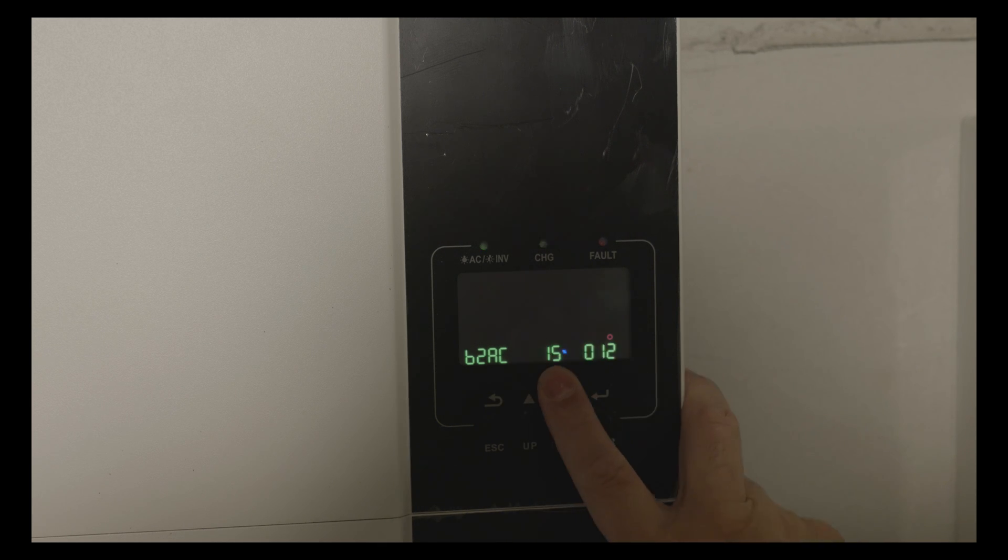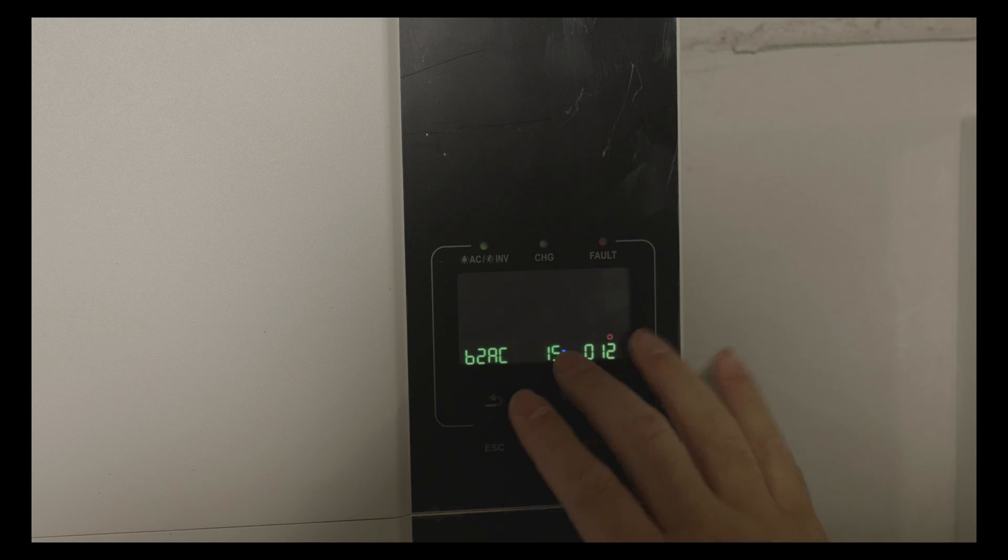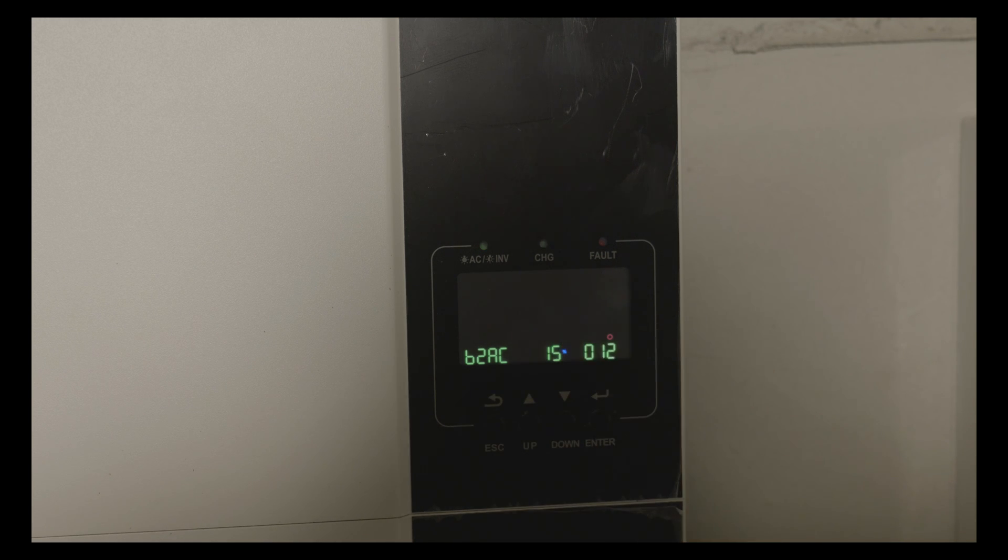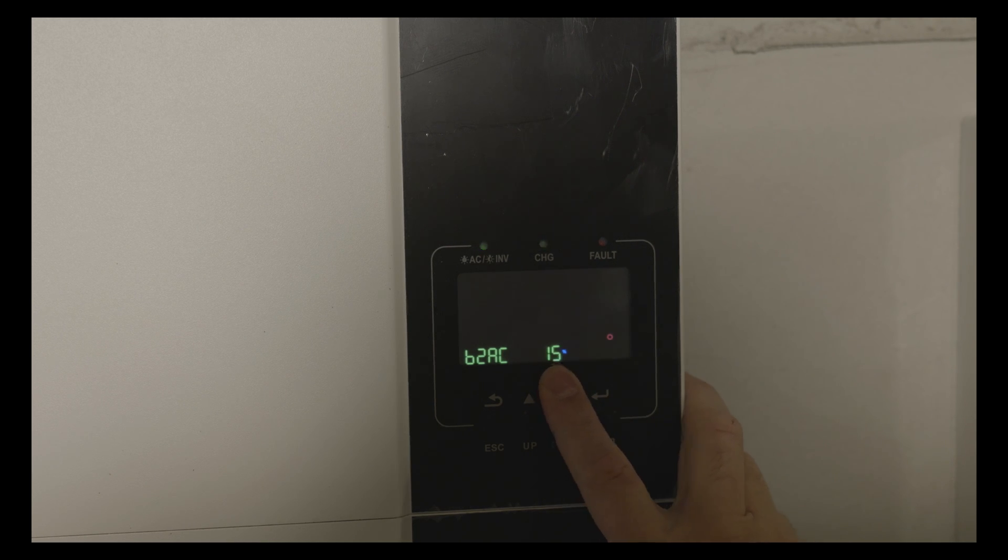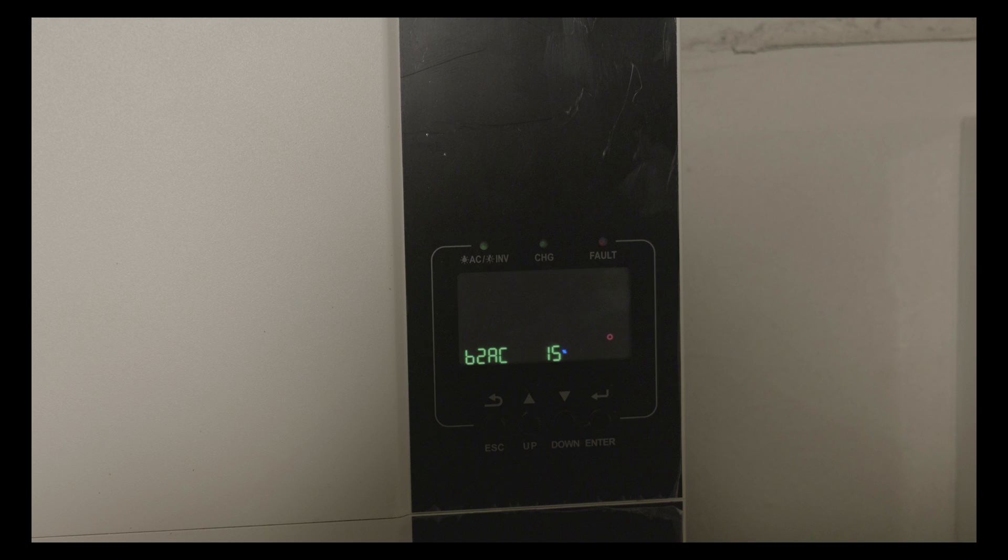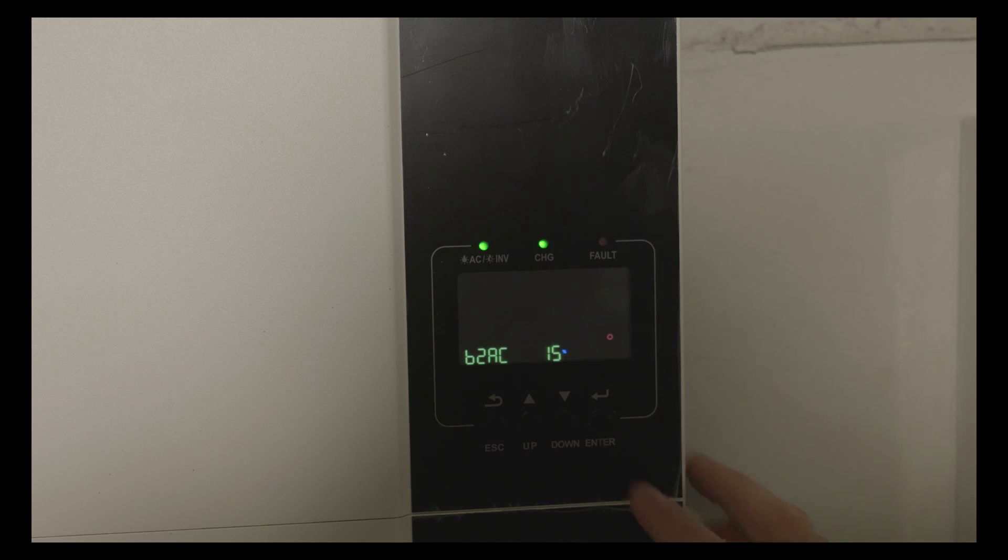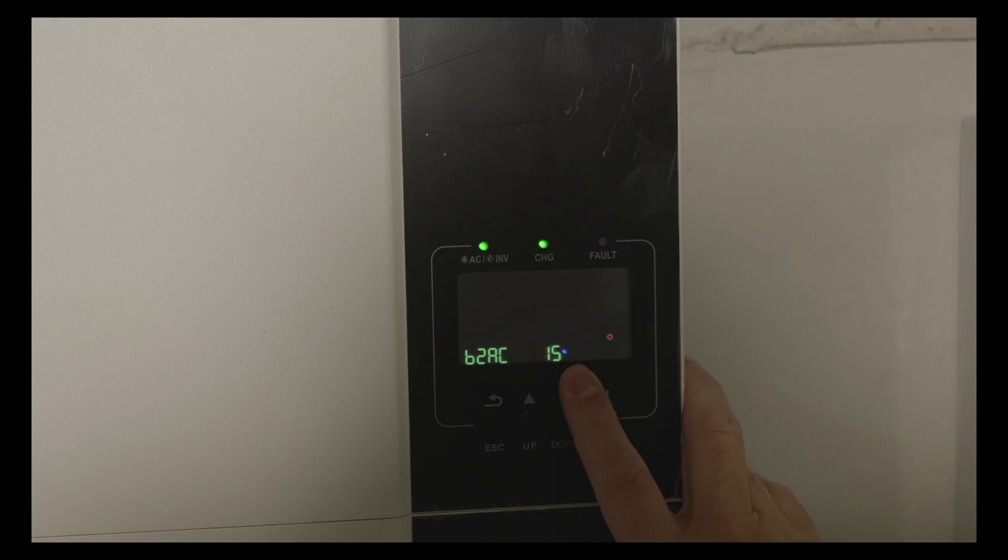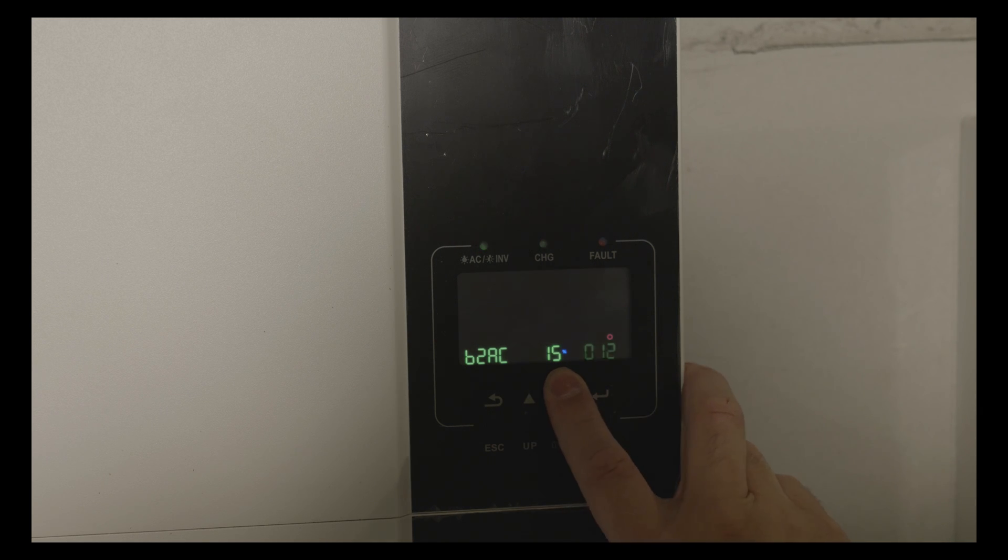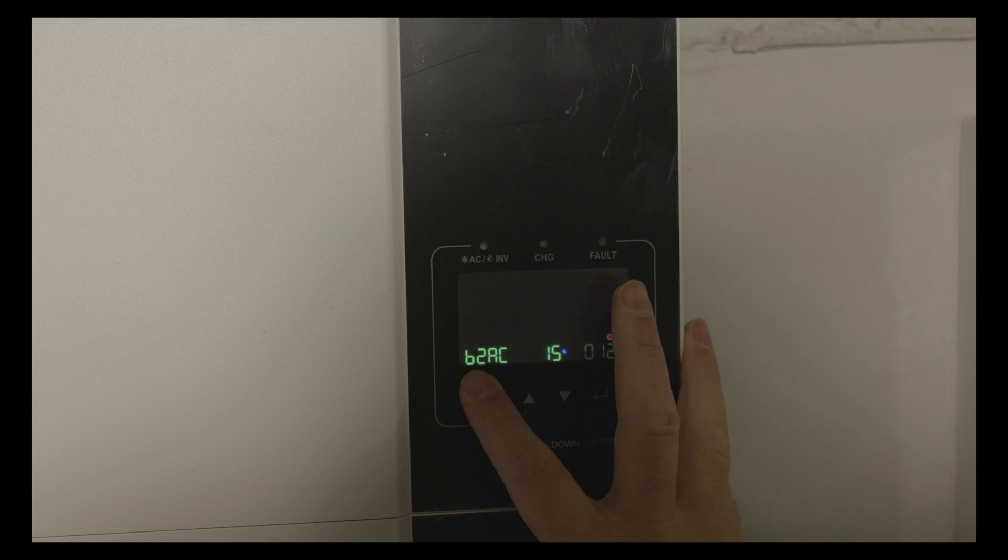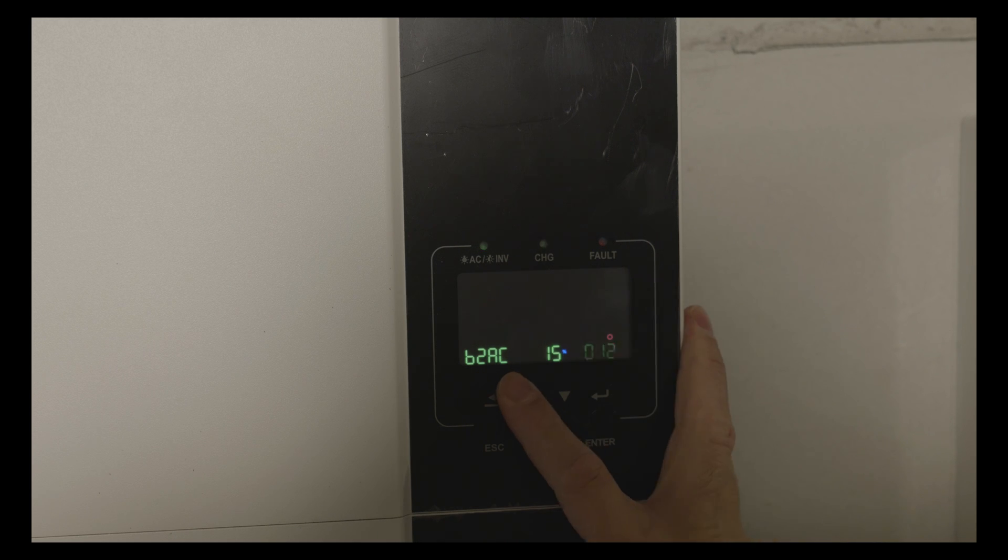Battery to AC: this option I set it to 15%, so when the batteries reach 15% it will switch back to utility. In my case this option is in 15%, but if you are using US2 option in the battery type it will be in voltage.